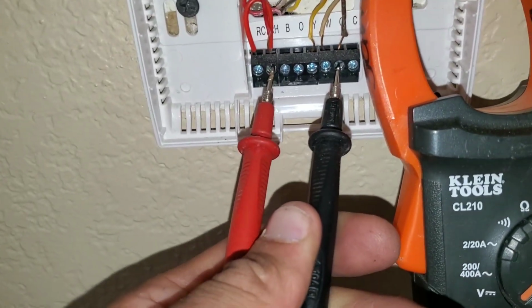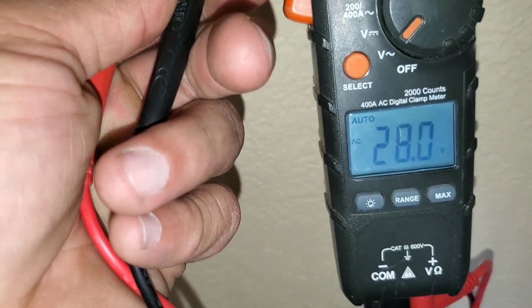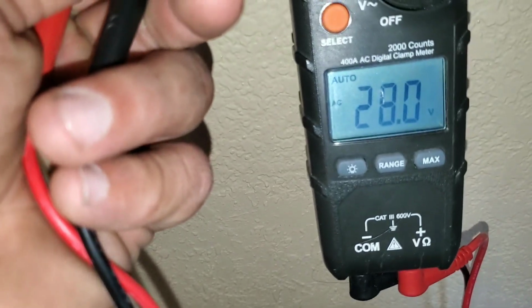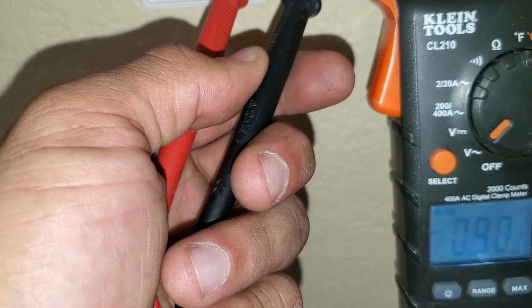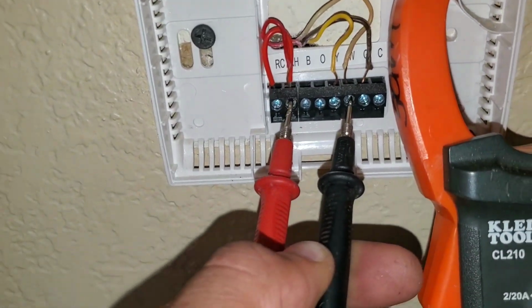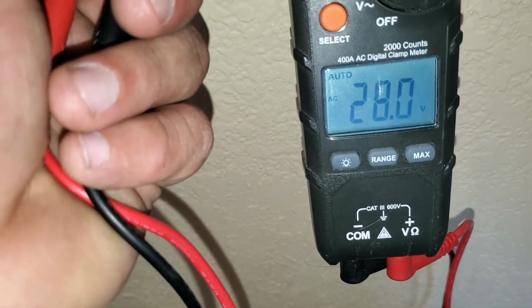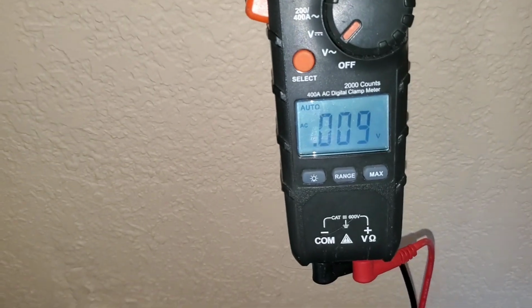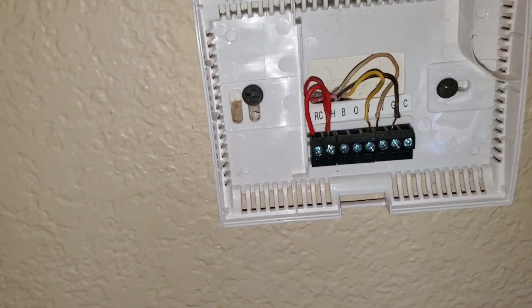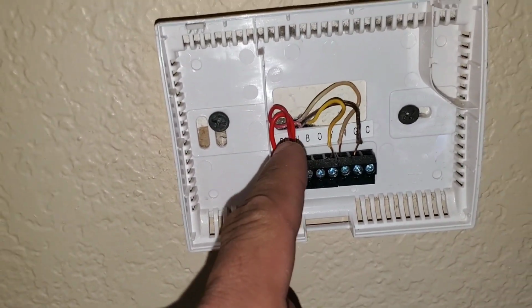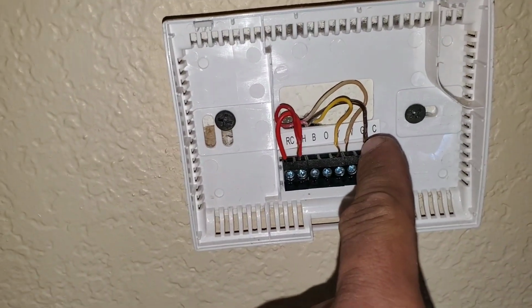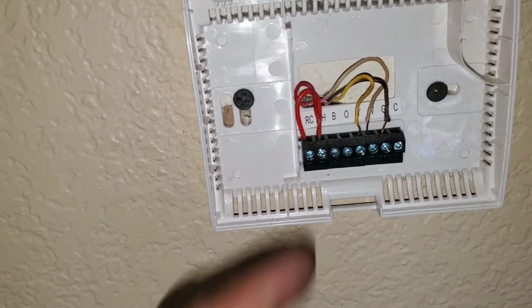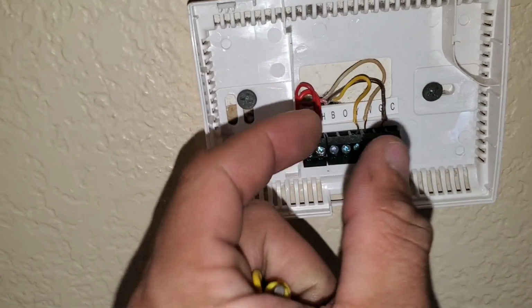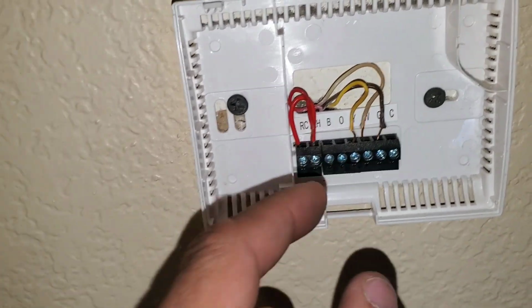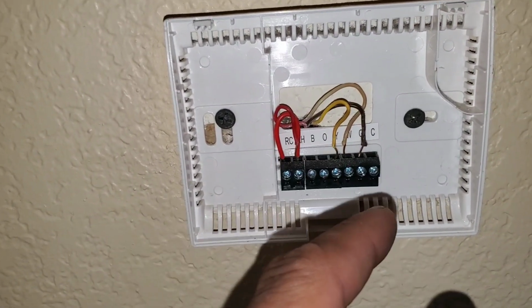Do the same for my G terminal, which is going to be my blower. So I do have voltage for my blower. The W is going to be for your heat. So I do have voltage coming into this thermostat. Now I'm going to do a very basic test. What we're going to do is we want to jump our R and our G terminal, which is going to be our blower. You can remove your wires and just tap them together and tie them in. That will engage your blower at your return.